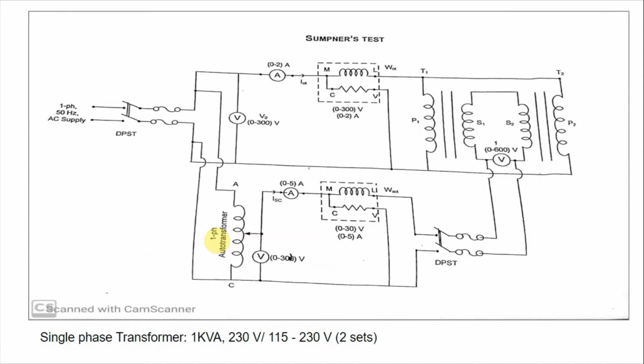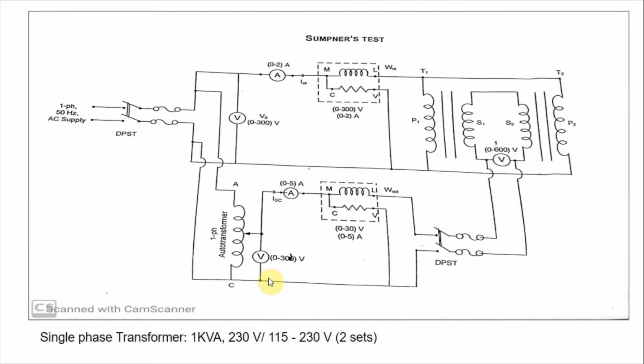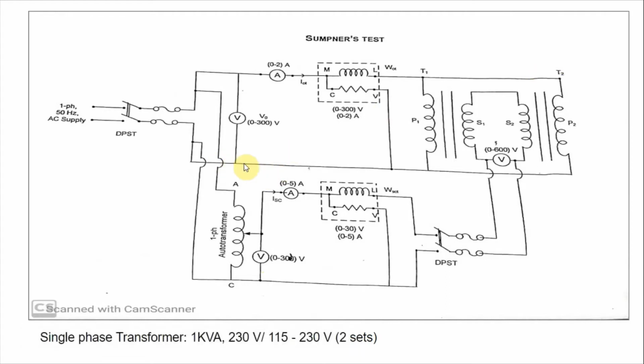Before explaining the principle, I'll just tell what are the initial positions of various switches and the auto transformer here. The DPST will be in the open condition. This DPST will also be in the open condition. The auto transformer is kept at minimum position. This test requires two identical transformers. Both the transformers are connected to supply such that one transformer is loaded on the other transformer.